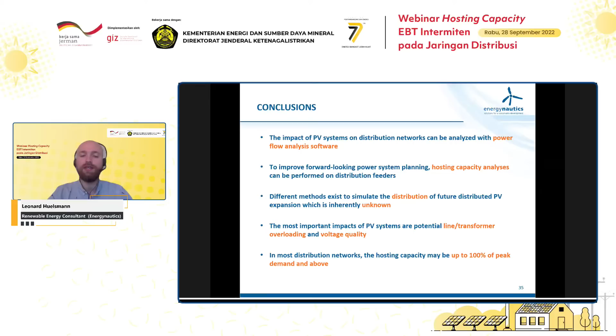And what we generally observe for most distribution networks that we have looked at around the world is that the hosting capacity is typically up to 100% of peak demand and above. So if you have a certain distribution feeder with maybe 10 megawatt of load, then typically at least you should also be able to add 10 megawatt of distributed generation to that network. So we are going to speak more on these things in the other sessions.